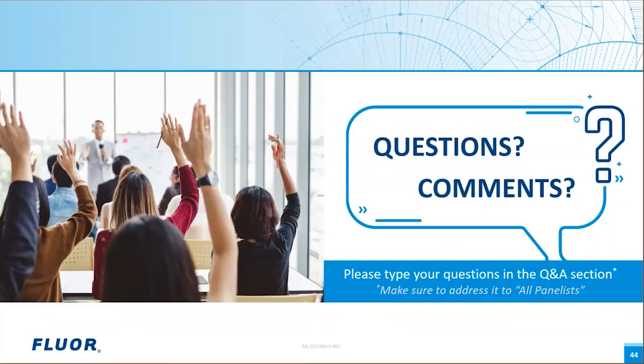Okay, that's a very good question. We've had a few clients with the same situation. The one thing I start off with, like I said in my presentation, I look for the low-hanging fruit, and taking water that's available to me and putting it into the cooling tower for makeup is the first thing I want to look at. What we did on one client, a refinery up in the Midwest, we took the wastewater coming out of the plant. Instead of treating it in a conventional wastewater treatment, biological treatment system, we used what is known as an MBR, membrane biotreatment, which is essentially an ultrafilter. So the water coming out of this wastewater plant is essentially very clean. So instead of discharging it to the stream, we treated that and sent it back to the cooling tower.